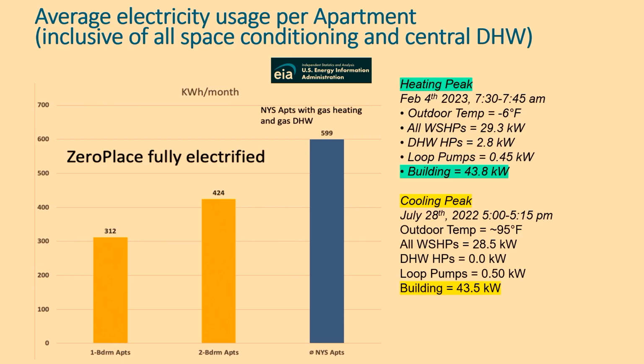Looking at peak numbers here, the original heating load ladder was 1,100 kW. Then they put GEO in instead of air source, and it reduced it to 343 kW. The most building peak demand in heating, and interestingly about the same in cooling, was 43 kW, just 4% of the original load ladder with air source heat pumps.